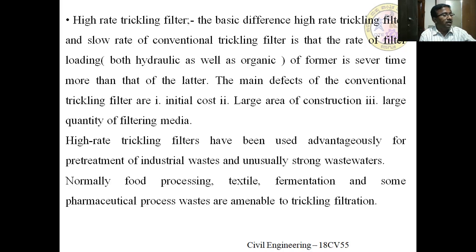And also the depth of the slow rate trickling filter is 1.5 to 3 meter, but in the high rate trickling filter it is usually 1 to 2 meter. Recirculation rate is 0 in a slow rate or conventional trickling filter, but here the recirculation rate is 1 to 3 in the high rate trickling filter.